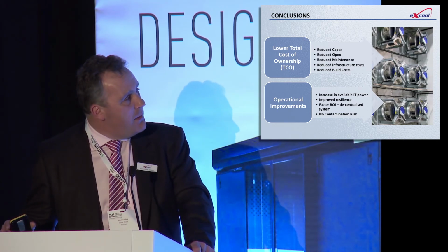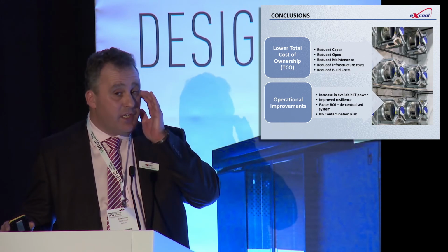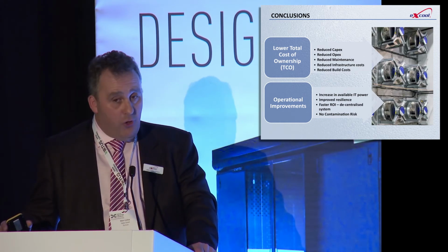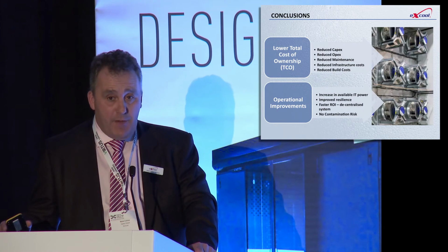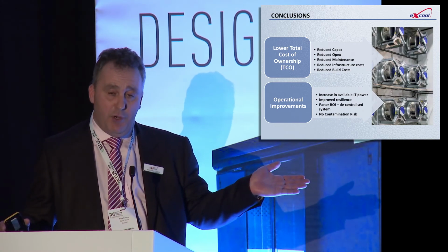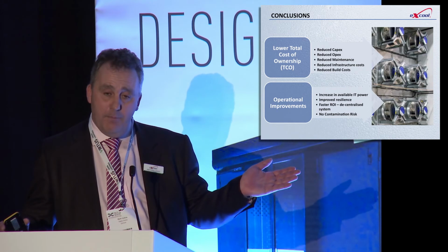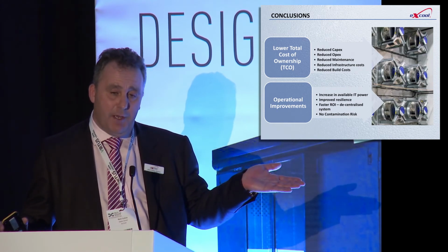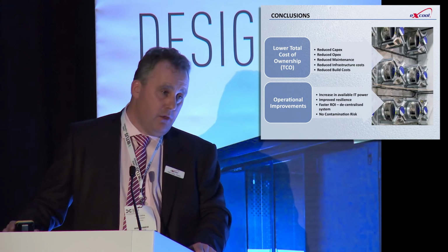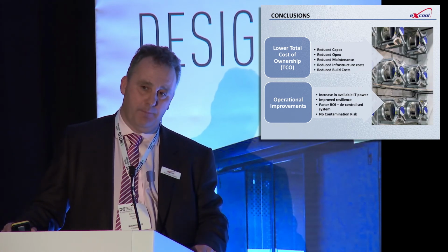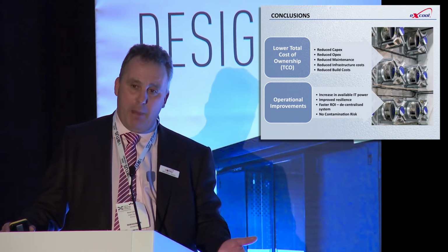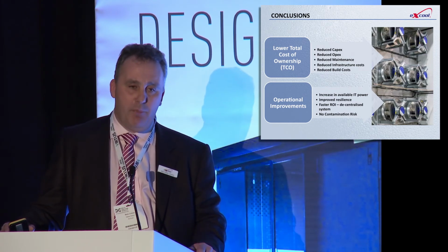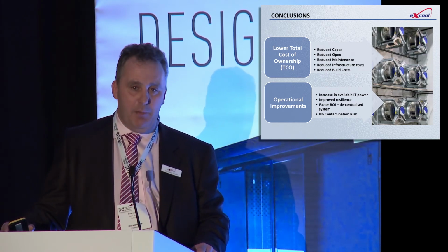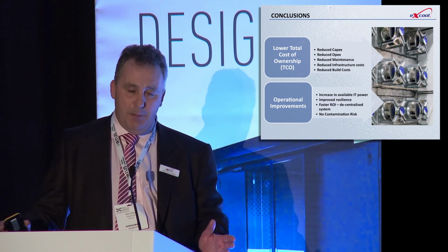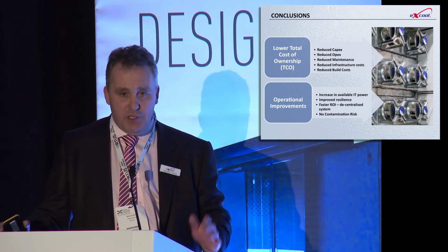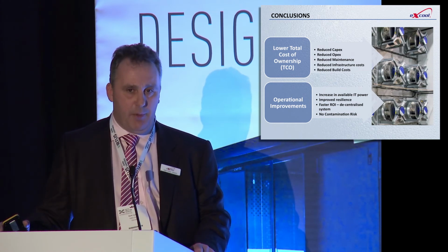In terms of operational improvements, there's an increase in available IT power and improved resilience. Again, it's a bunch of fans and pumps. If we lose one of these fans, you generally would go N+1 as a minimum. But if we lose one fan on a large unit, we've lost 1/16 of its cooling capacity on one unit. Same with the pumps. We have 4 pumps on each of the units, so if we lose one pump, we lose 25% of the cooling ability of that one unit. And all that simply happens is an alarm is raised and the other units increase their speed marginally to accommodate it.